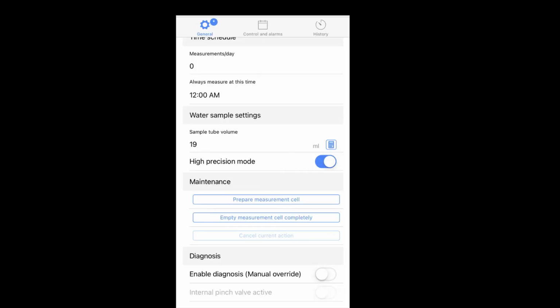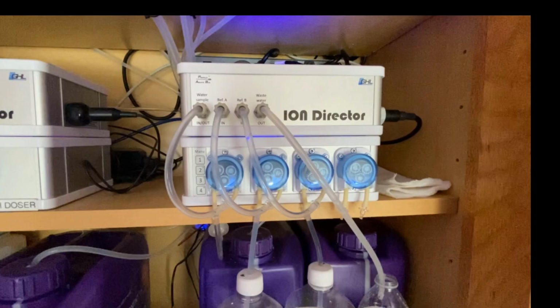Now click Save. With the pumps assigned and the water sample volume set, the last step is to acclimate the ion probe. Click on the Prepare Measurement cell. When you do this, the ion director is going to prepare the probe for use. It is important to inspect the ion director after you click the Prepare Measure cell, as it is now filling the chamber with your tank water, reference A and reference B solution. If you see any leaks, you should power down the unit, dry off any wet components, correct the issue, and try again. Water can damage the ion director.